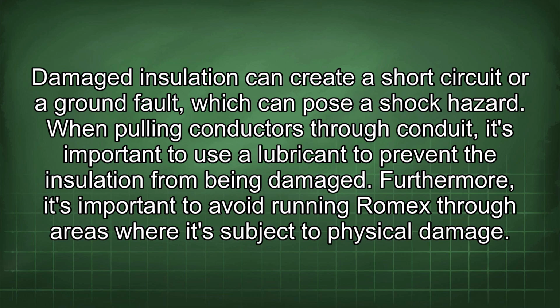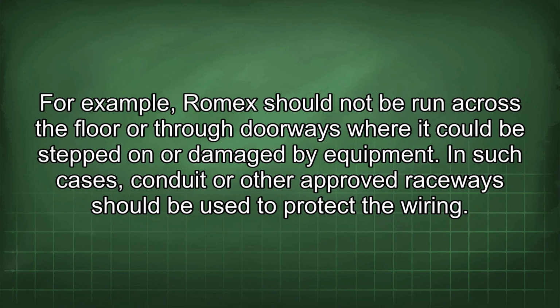Furthermore, it's important to avoid running Romex through areas where it's subject to physical damage. For example, Romex should not be run across the floor or through doorways where it could be stepped on or damaged by equipment. In such cases, conduit or other approved raceways should be used to protect the wiring.